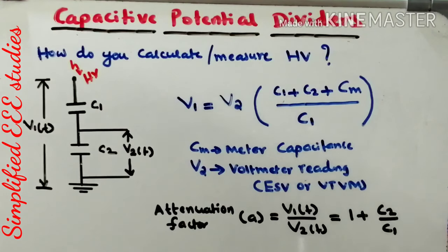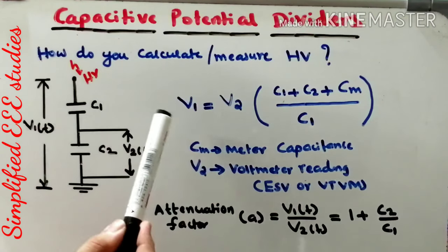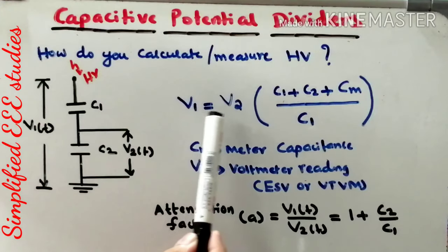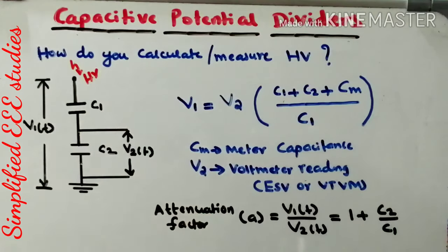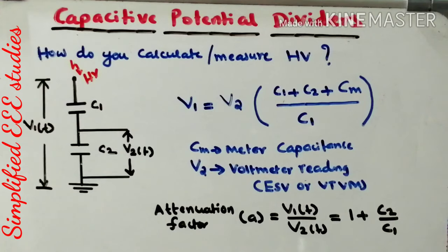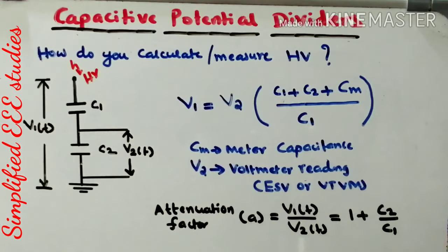Now let us explain how to calculate the voltage which you operate externally — this high voltage that has to be measured. Let me call the high voltage applied V1. V1 = V2 × (C1 + C2 + Cm) / C1. V2 is the reading obtained from the Electrostatic Voltmeter or VTVM. C1 and C2 values are known from the design. The meter capacitance Cm is approximately 50 pF. By substituting all values, you can determine the high voltage applied externally. This is a simple method to measure high voltage externally.